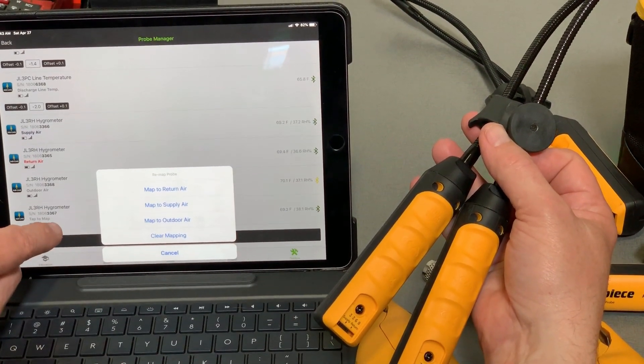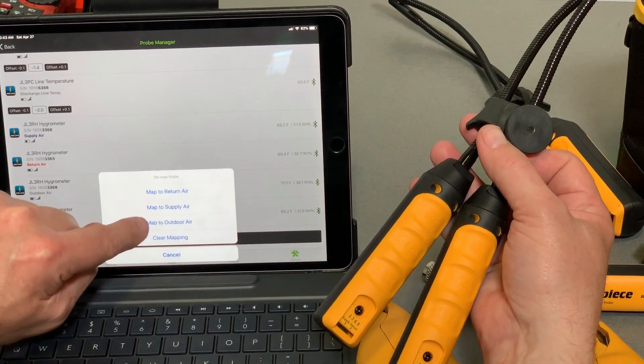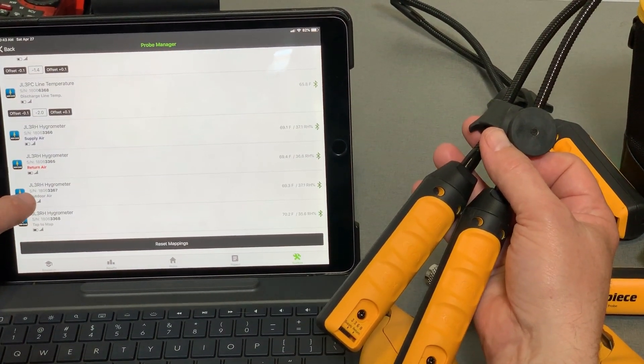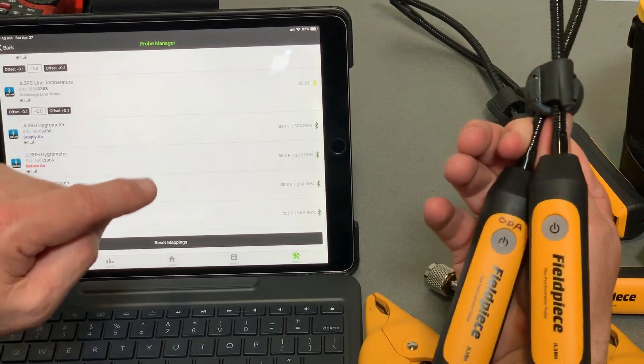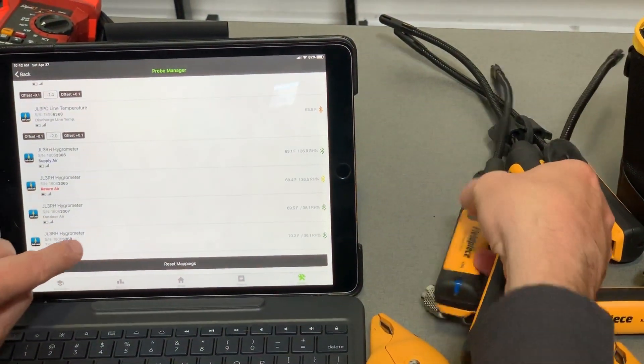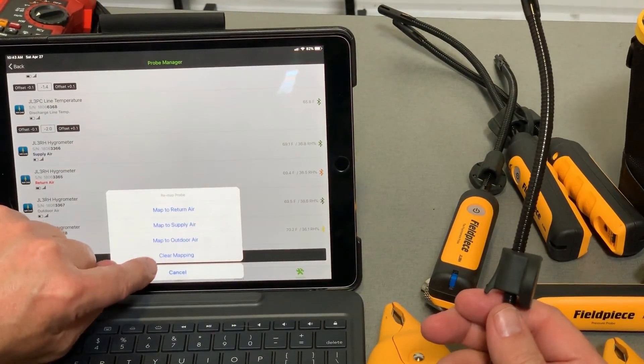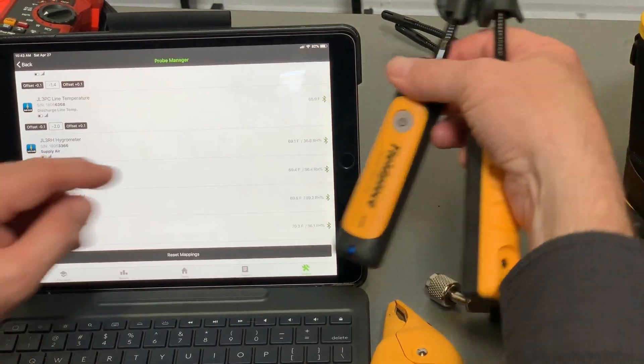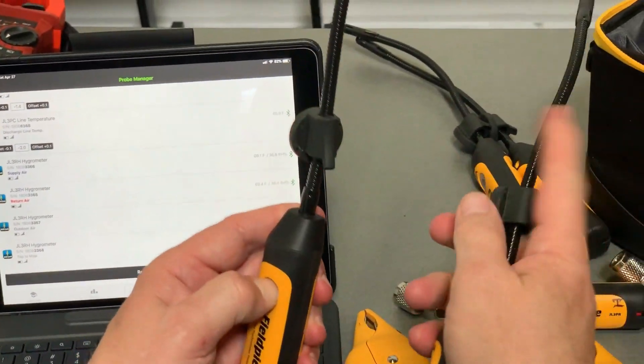I can tell it what its job is. Every single probe — if I tap on a hygrometer — I can map it to supply, return, outdoor air, or clear the mapping. In this case I'm going to map my 67 back to outdoor air, so I'll click on that. Now you can see 67 went back to the top — that's the one I have marked ODA. I'll go ahead and clear the mapping on the spare one and then power it off, so it's out of the circuit because I don't really need it right now.